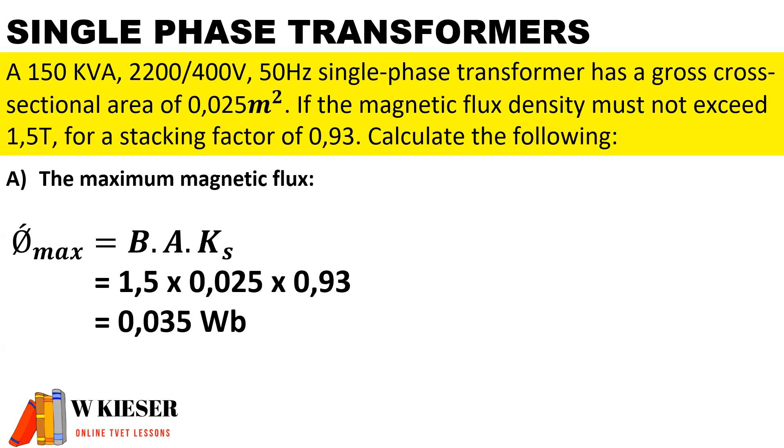In this calculation: a 150 kVA, 2200 on the primary and 400 volts on the secondary, 50 hertz single-phase transformer has a gross cross-sectional area of 0.025 meters squared. If the magnetic flux density must not exceed 1.5 Tesla for a stacking factor of 0.93, we need to determine the following.